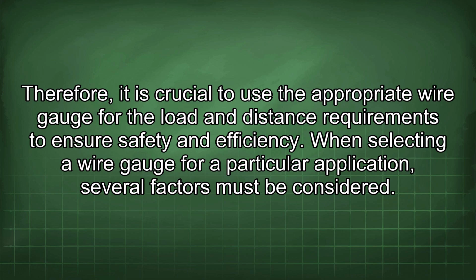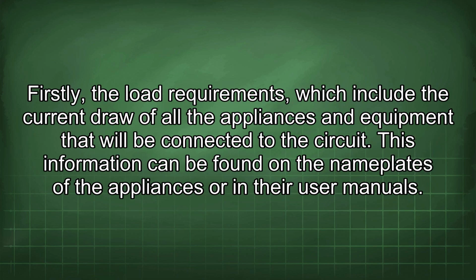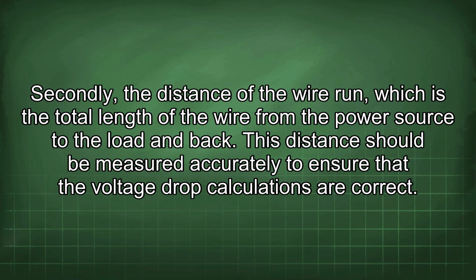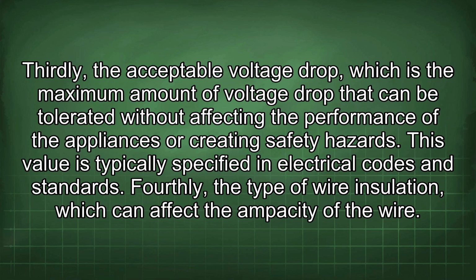Therefore, it is crucial to use the appropriate wire gauge for the load and distance requirements to ensure safety and efficiency. When selecting a wire gauge for a particular application, several factors must be considered. Firstly, the load requirements, which include the current draw of all the appliances and equipment that will be connected to the circuit. This information can be found on the nameplates of the appliances or in their user manuals. Secondly, the distance of the wire run, which is the total length of the wire from the power source to the load and back. This distance should be measured accurately to ensure that the voltage drop calculations are correct. Thirdly, the acceptable voltage drop, which is the maximum amount of voltage drop that can be tolerated without affecting the performance of the appliances or creating safety hazards.